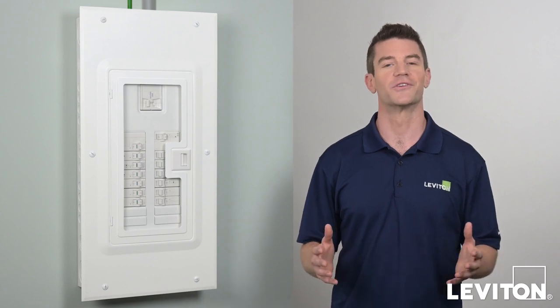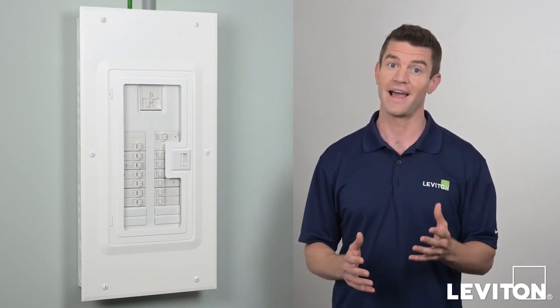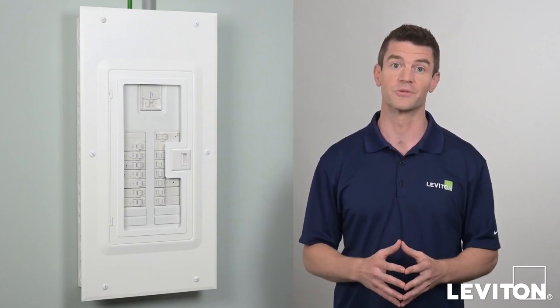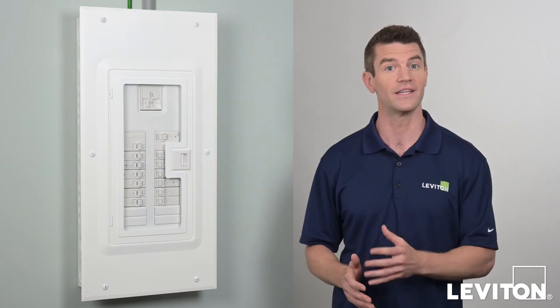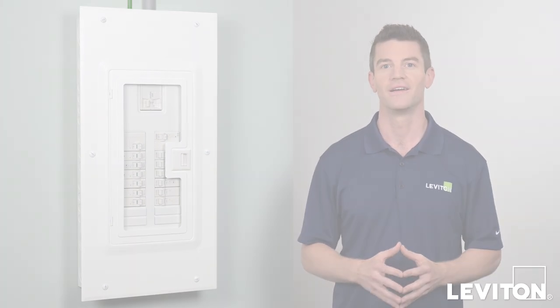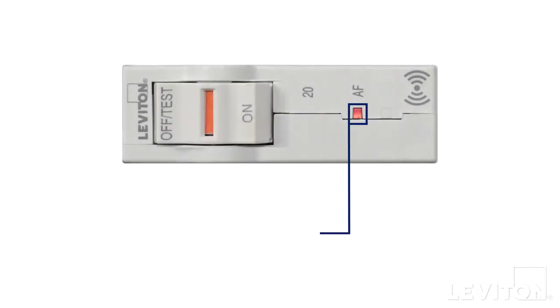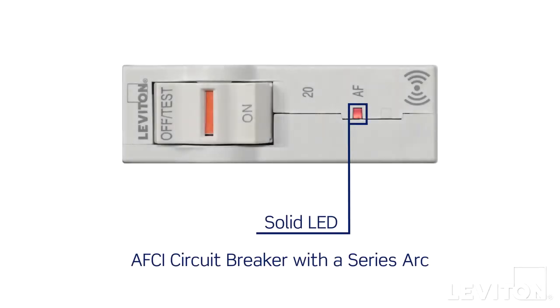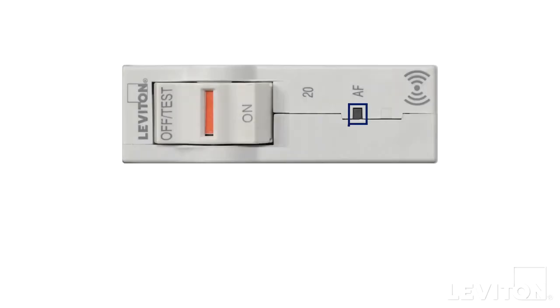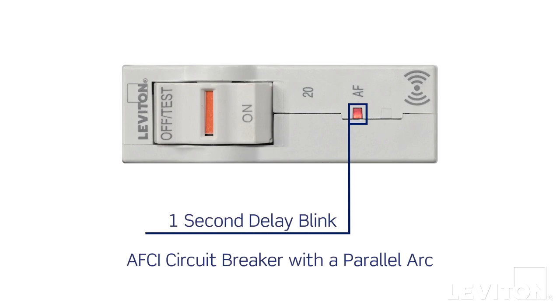If the arc fault circuit breaker experiences an arc fault, it can actually tell the difference between a series and a parallel arc. During a series arc, the AF window will light up with a solid LED. If the arc fault circuit breaker experiences a parallel arc, the AF window will display a blinking light with a one-second delay.